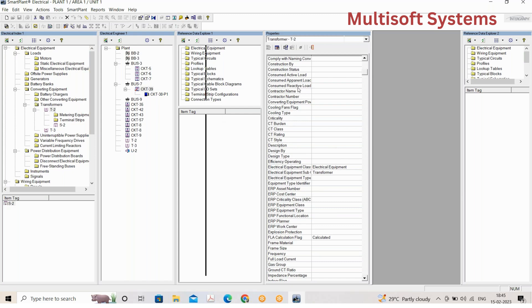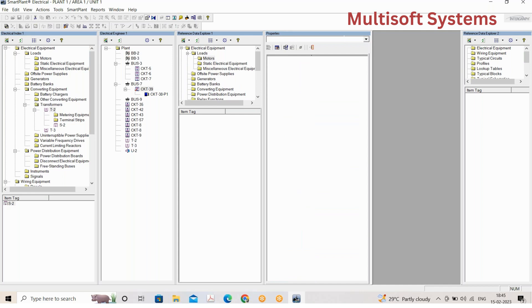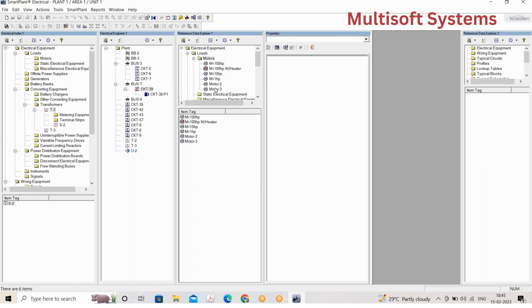The most important window is the Reference Data Explorer. It also has a tree structure with different folders — you can see motors listed there. We use Reference Data Explorer as a reference: if you have multiple motors with the same rating and same properties, you create one motor here and use it to create multiple motors with the same ratings, saving significant time for bulk equipment creation.